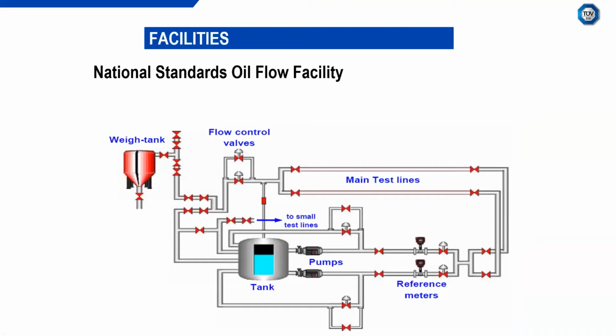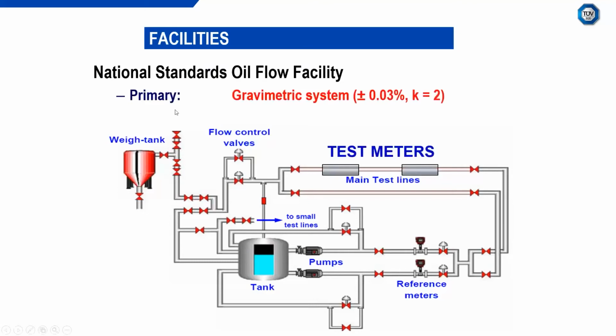The oil flow facility uses a gravimetric primary reference. You can see that there, it's the weigh tank. We also have positive displacement reference meters as our master meters, which is the secondary reference. For low viscosity fluids, that's where we install the test meters, apologies. For the low viscosity fluids, the primary gravimetric system has an uncertainty of 0.03% at K equals 2. The PD master meters have an uncertainty of 0.08% at K equals 2.